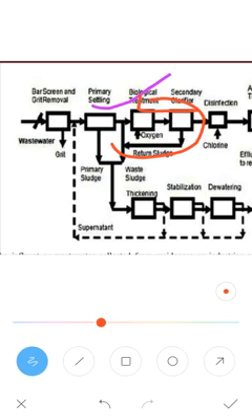In this sludge digestion process, the wastewater sludge is subjected to thickening. The thickness of this sludge is allowed to increase. That is called thickening, where the number of solid sludge particles keeps increasing by separating from the liquids. The liquid and the sludge get separated. The liquid which rests over the solid sludge particles is removed. That removed liquid is called supernatant.